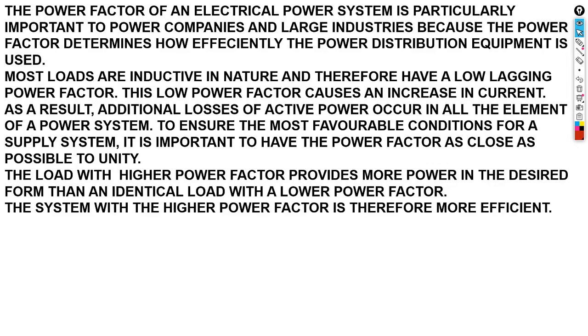The power factor of an electrical power system is particularly important to power companies and large industry because it determines how efficiently the power distribution equipment is used. Most loads are inductive in nature and therefore have a lower lagging power factor. This low power factor causes an increase in current, resulting in additional losses of active power. To assure the most favorable conditions, it's important to have a power factor as close as possible to unity — like a pure resistor.